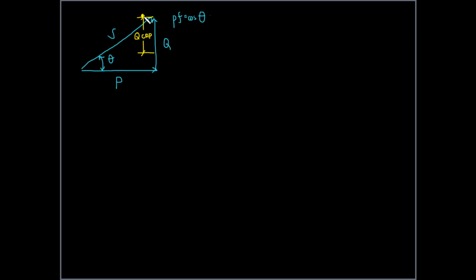So this is actually going to be the decrease in the value of your reactive power when you have installed already your capacitor banks. So if there's going to be a decrease, you will now have a new or final value of Q being the original value of Q minus the Q offered by your capacitor.